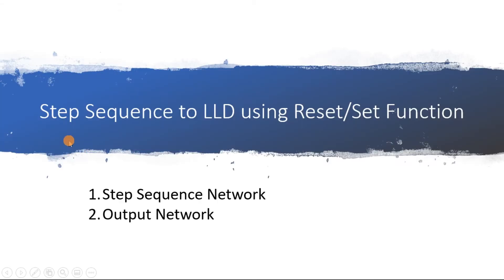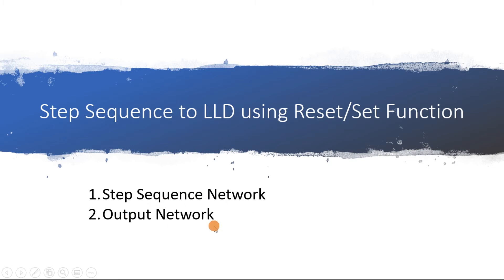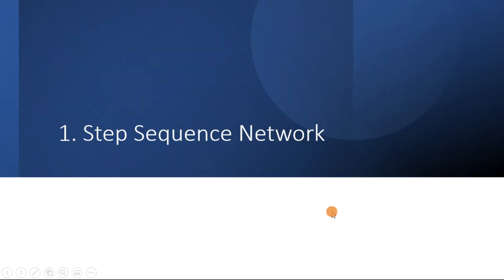We are going to move this step sequence to a ladder logic diagram by using the Reset/Set (RS) function. In order to use this RS function, you need to understand there are two networks available for this transformation. The first is the step sequence network, which consists of the memories and the steps. The second is the output network, which consists of the output conditions for each step. We start with the first — the step sequence network.